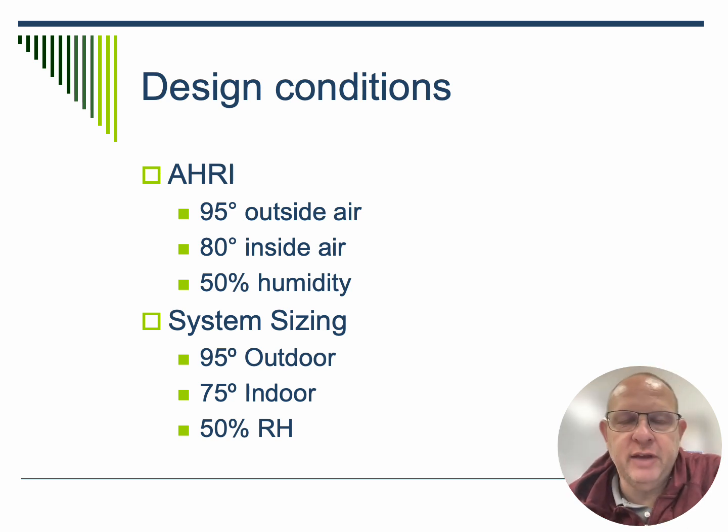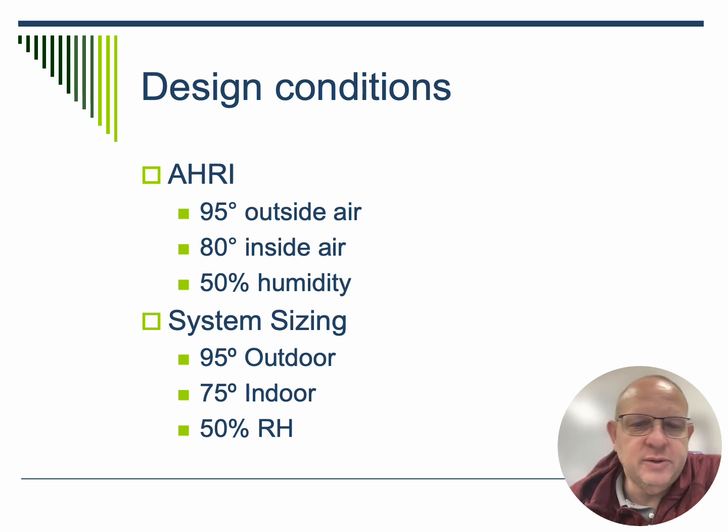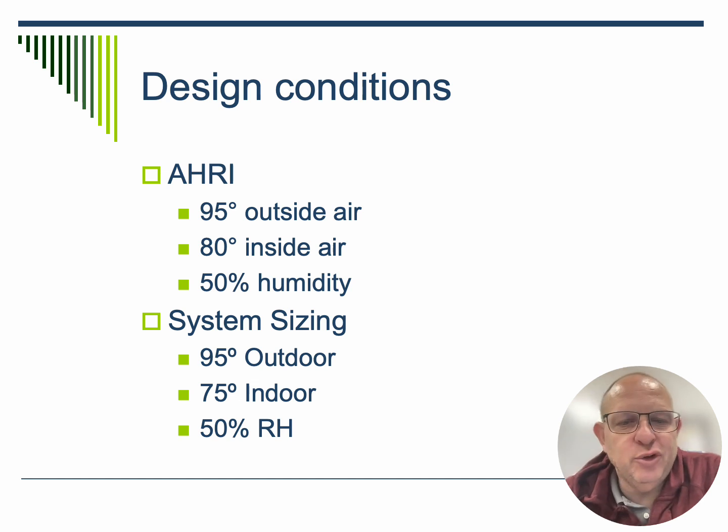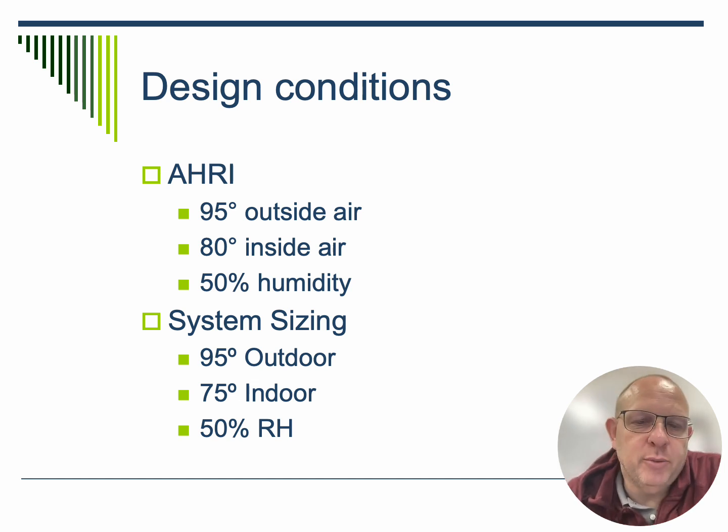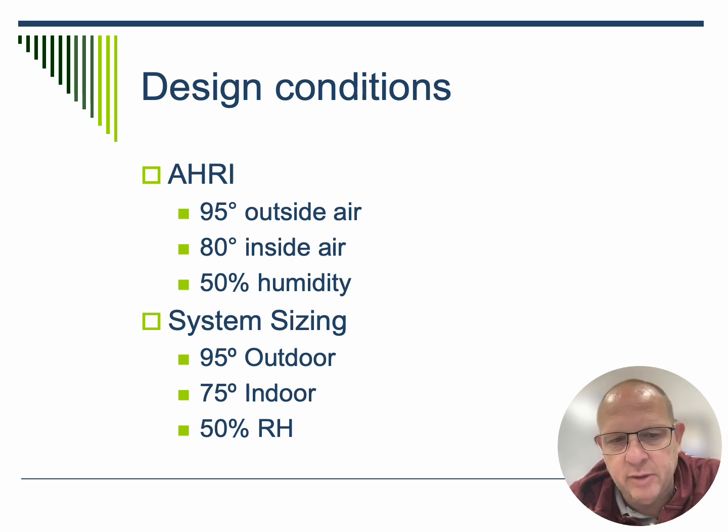So manufacturers will give their piece of equipment to testing facilities. Either they'll do it in-house or send it out, and then they'll get nominal BTU ratings, or nominal British thermal units and capacities, that these units will be running in. These AHRI conditions are 95-degree outdoor temperature, 80 degrees indoor temperature, and 50% relative humidity when we're looking at the AHRI standard conditions for ACs that are out there.